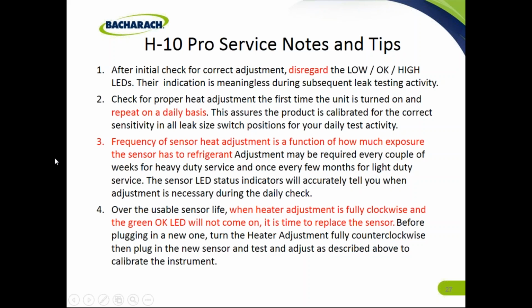Check for proper heat adjustment the first time the unit is turned on, and repeat on a daily basis. This assures the product is calibrated for correct sensitivity for all leak sizes, size switch positions for your daily test activity. Frequency of sensor heat adjustment is a function of how much exposure the sensor has to refrigerant. Adjustment may be required every couple of weeks for heavy-duty service and once every few months for light-duty service. The sensor LED status indicators will accurately tell you when the adjustment is necessary during a daily check. Over the usable sensor life, when the heater adjustment is fully clockwise and the green OK LED will not come on, it's time to replace the sensor.